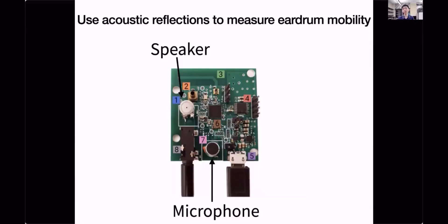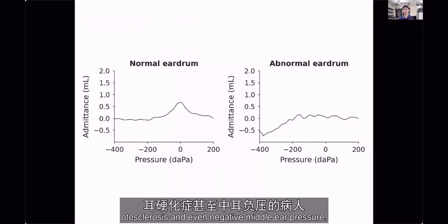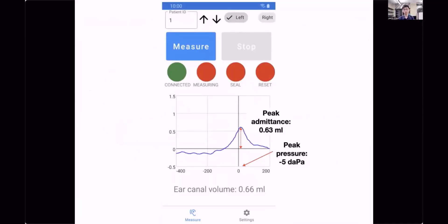Now, to evaluate our device, we conducted a study on 50 pediatric ears and did this test in parallel with a commercial tympanometer. And we targeted patients with a variety of middle ear disorders, including patients with ear tubes, eardrum perforations, otosclerosis, and even negative middle ear pressure. We compared the systems on key metrics here. So we compared the height of the tympanogram with the peak admittance, the peak pressure, so at what pressure the peak of the tympanogram was, and also the ear canal volume that was measured using the device.